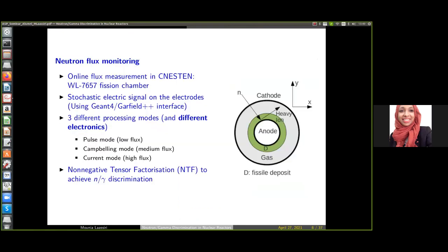So now, let's talk about some of my nuclear work. The first part will be dedicated to my PhD work. As you know, for efficient exploitation of research reactors, it is important to discern the neutron flux distribution inside them with the best possible precision. For this reason, fission chambers are used to detect and measure the neutron fluence rates over the exposure time. I mean, neutron flux monitoring.